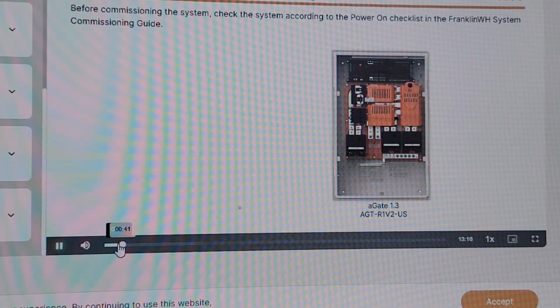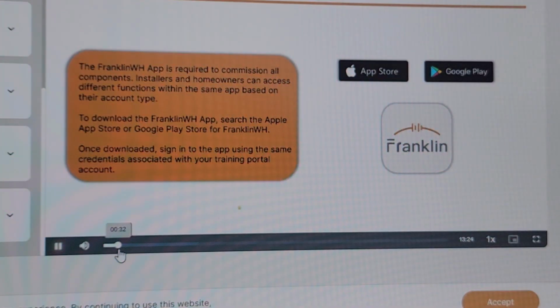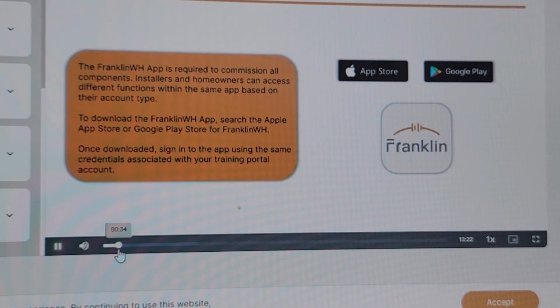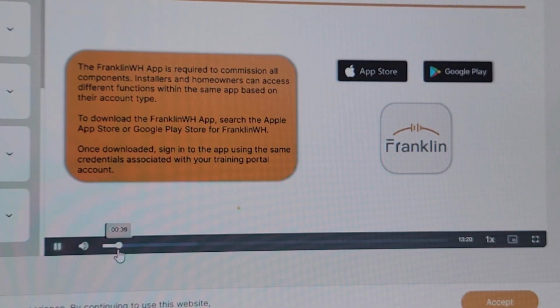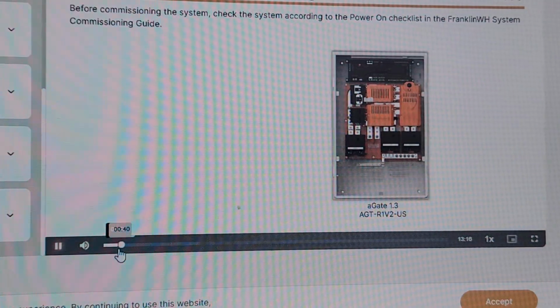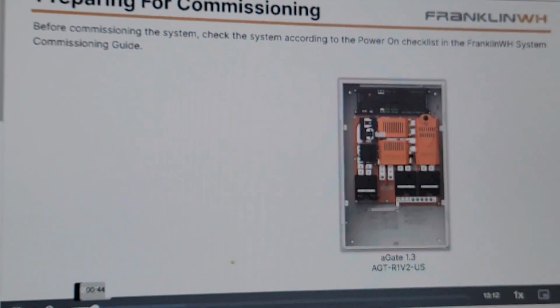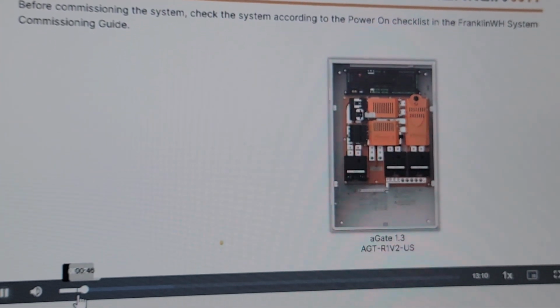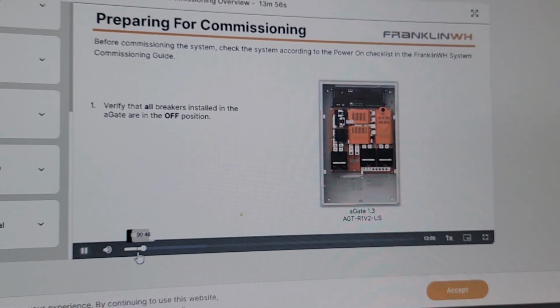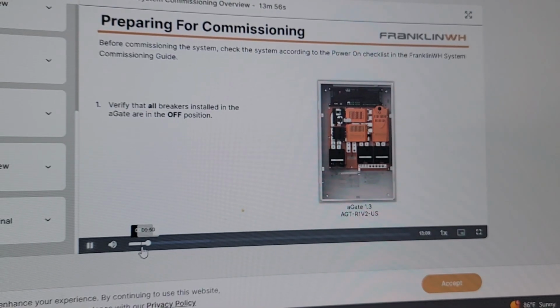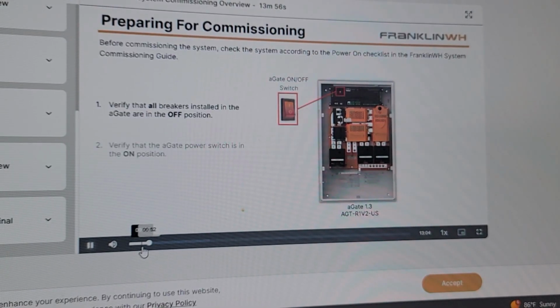Before commissioning the system, once downloaded, sign into the app using the same credentials associated with your training portal account. Before commissioning the system, check the system according to the Power On checklist in the FranklinWH System Commissioning Guide. Step 1. Verify that all breakers installed in the A gate are in the off position. Step 2. Verify that the A gate power switch is in the on position.